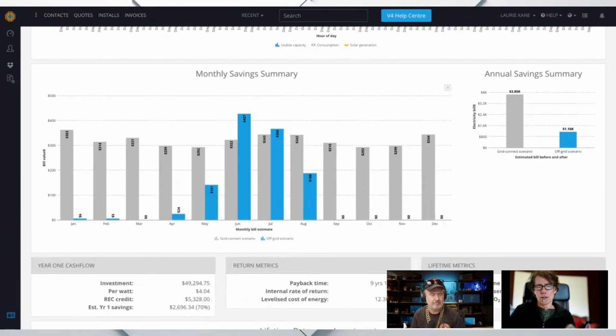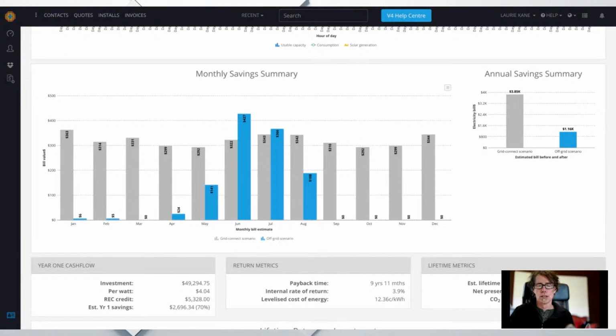That's right. Yeah. So there is a lot of variability, and with an online system like Solar Plus, we're pulling in weather data at a very localized level. So as soon as the address goes in, we're pulling in solar radiation and weather data for that site, and the radiation data is a 10 square kilometer grid across the globe. So anywhere in the world, we can do the modeling for that site using localized radiation data and the closest weather station. So we pull weather from the closest weather station that's had some reliable weather data for a few years.